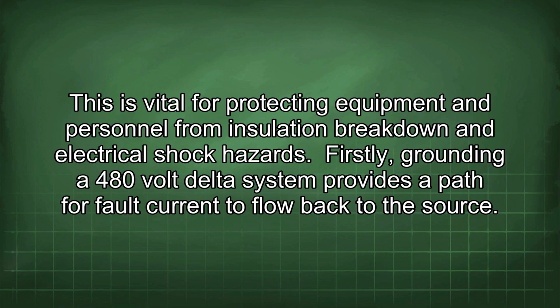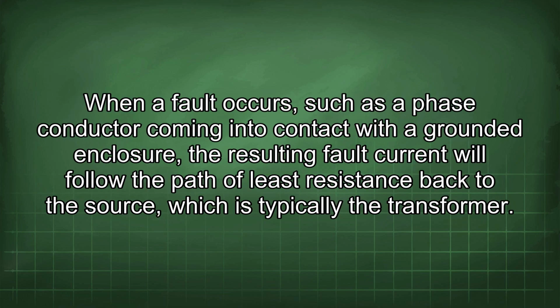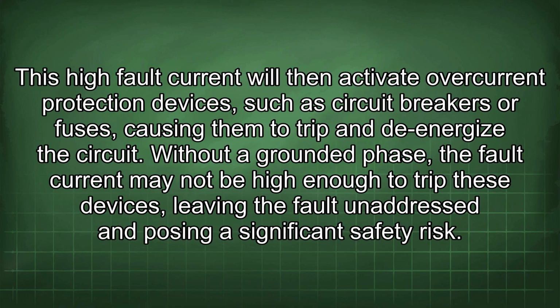Firstly, grounding a 480-volt delta system provides a path for fault current to flow back to the source. When a fault occurs, such as a phase conductor coming into contact with a grounded enclosure, the resulting fault current will follow the path of least resistance back to the source, which is typically the transformer.